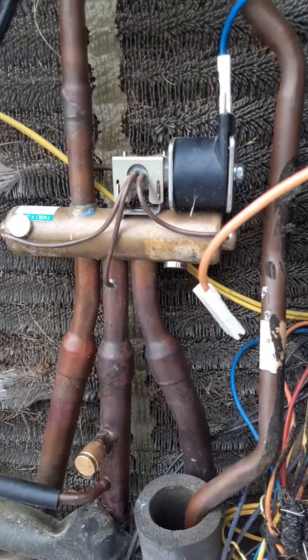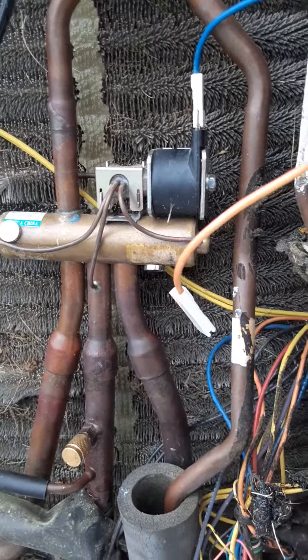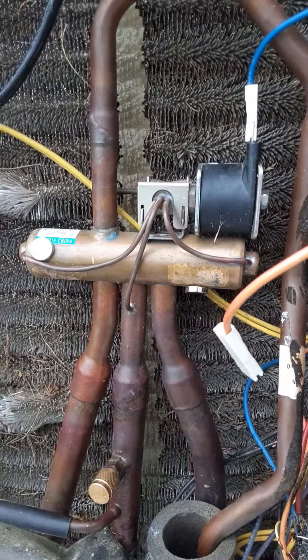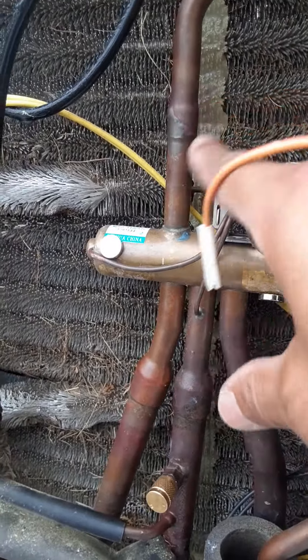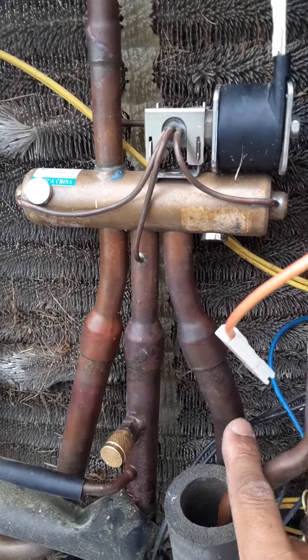Doing a quick video on a two-ton Trane heat pump reversing valve. Right now I have it de-energized. I took the orange wire off so it's in the heating mode. It just reverses the flow of refrigerant. Refrigerant comes up and comes down this line, which was the low side line, and goes to the evaporator core.